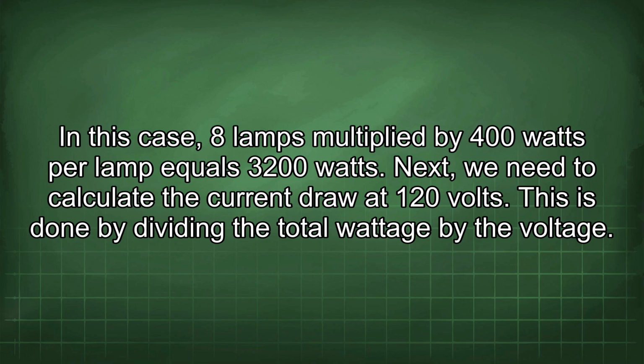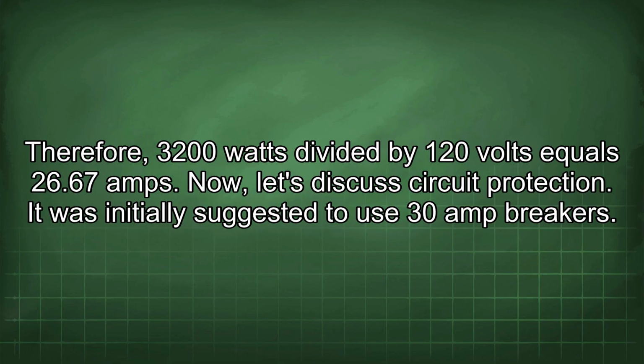Next, we need to calculate the current draw at 120 volts. This is done by dividing the total wattage by the voltage. Therefore, 3,200 watts divided by 120 volts equals 26.67 amps.